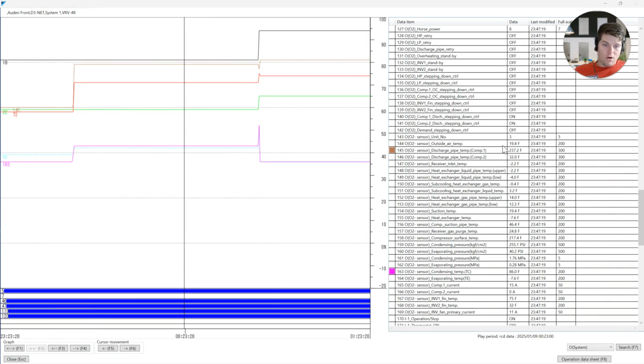What do we also know about discharge temperature? Discharge temperature gives us an idea of the compression process within the compressor. This is a health check, guys, right? This is what the compressor does when he goes to get his prostate checked. They're looking at discharge superheat, right? In this discharge superheat check, we're seeing 237.